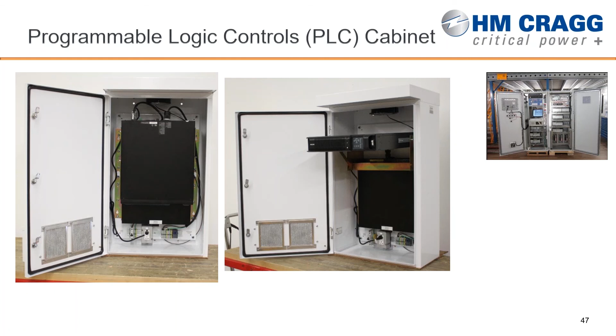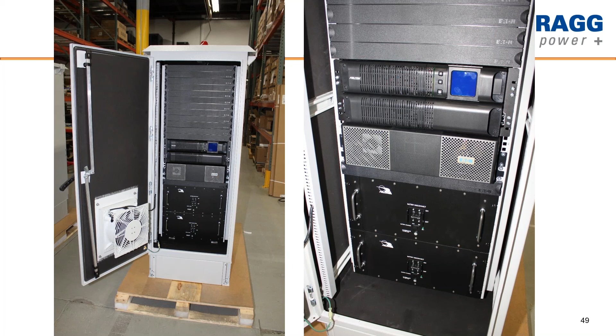Yeah, so this was a really unique opportunity for us. This is going directly at the wellhead on an oil field. So the requirements they had was 6 kVA of capacity with a 120 volt input and a 120 volt output. So we utilized a high temp UPS with a main input transformer to supply the 6 kVA power. We've got about 4 hours of runtime in two 5U battery modules with dedicated chargers, and then a break-before-make bypass and output isolation transformer here.